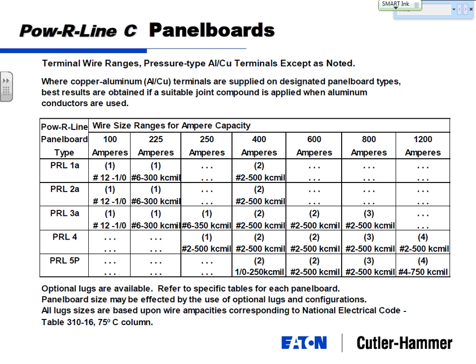Now, we could probably go through the rigors of testing it, but I don't know if anybody has dealt with UL; it's very expensive and time-consuming to test all the different configurations you can use to be able to expand these types of designs. And just to throw out a number, it might be $1 million in testing costs to come out with one switchboard design that can handle a 90 degree C cable.